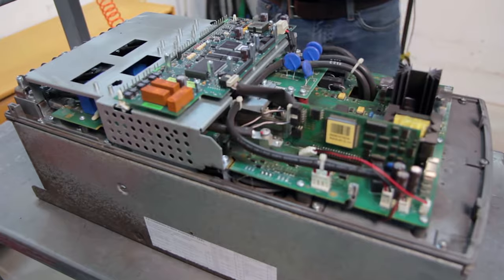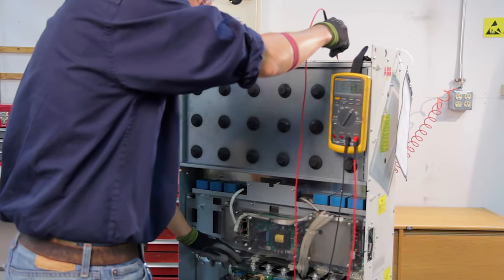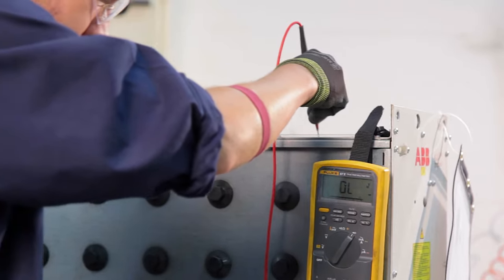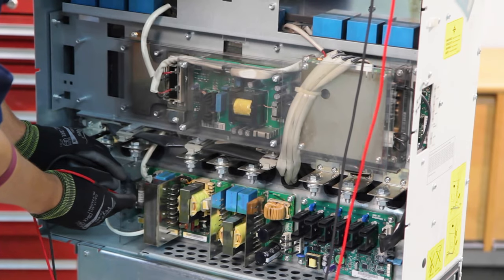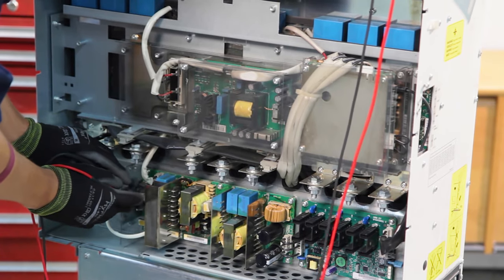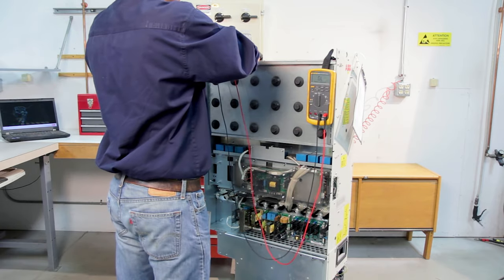The repair process starts with the technician performing a general condition inspection for dust, moisture, corrosion, or other environmental stress. To further troubleshoot the cause of the failure, the technician uses a multimeter to perform static checks. The technical inspection concludes with the identification of broken, damaged, or defective components.